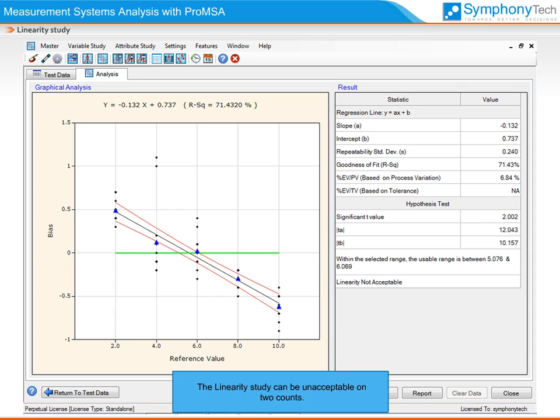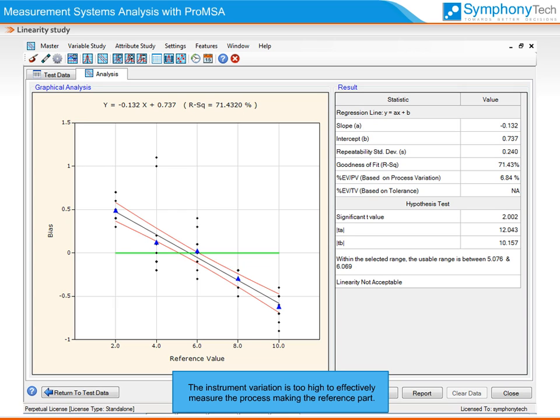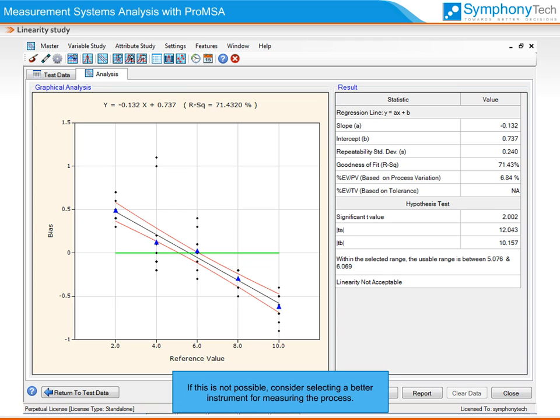The linearity study can be unacceptable on two counts. First, the percent repeatability could be high — the instrument variation is too high to effectively measure the process making the reference part. In such a case, the instrument may require maintenance or calibration to improve its repeatability. If this is not possible, consider selecting a better instrument for measuring the process.